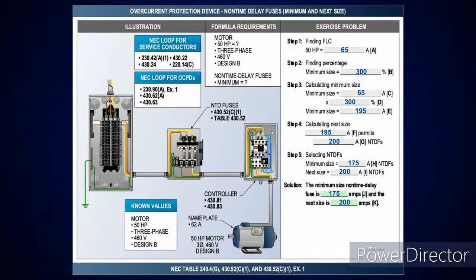All right. Now, the first one, everybody remember this. I'm going to go over this a little bit just to refresh everybody. I said anytime you're sizing your overcurrent protection devices or conductors, you want to use the amperage values that are in the tables in 430.247 through 250. And we get that permission over in 430.6(A)(1). Now, when I'm doing the overload protection, I'm going to look at 430.6(A)(2) and it's going to tell me to use the nameplate. All right. So I just want to make sure everybody remembers that.